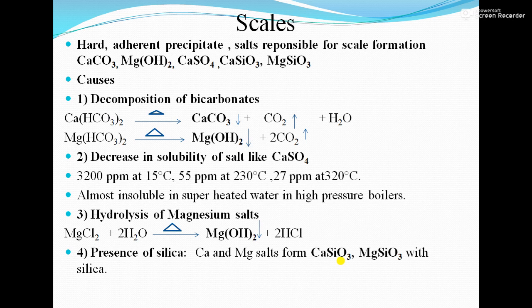The first cause of scale formation is decomposition of bicarbonates. If temporary hardness salts like calcium bicarbonate and magnesium bicarbonate are present, on heating they produce precipitates of calcium carbonate and magnesium hydroxide that stick to the boiler metal. The second cause is the decrease in solubility of salts like calcium sulfate — at 15°C, calcium sulfate has a solubility of 3200 PPM, which reduces to 55 PPM at 230°C.